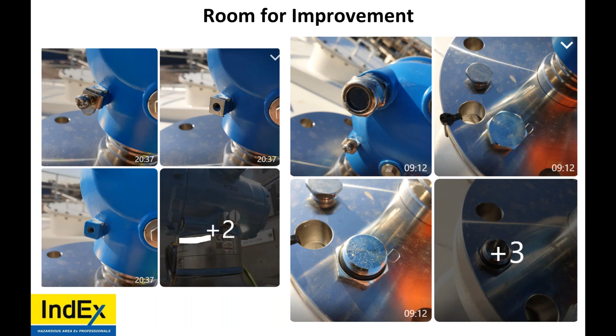Cable glands. Everybody likes to say they're easy. Why is it that there are always significant issues within our industry? Because people assume they are easy. Once again, the vendor—is there perhaps a lack of leadership? Perhaps they're managers, but maybe they don't have the competency to understand what they're looking at, or other human factors. With the cable tags right up against the cable glands, there's now no way to back the cable gland off for detailed inspection, which is a requirement.